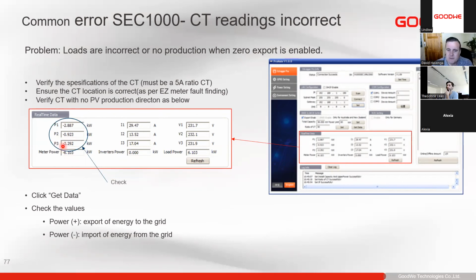If you look here in this graph, at the bottom you see the refresh button. You can press the refresh button, and that gives us a snapshot of what we can see from the smart meter. All these values need to be negative. A negative value indicates consumption from utility. We first need to make sure we are using the correct 5 amp secondary ratio CTs. If the CTs are wrong, we'll also get very strange readings here. But our readings should be aligned.